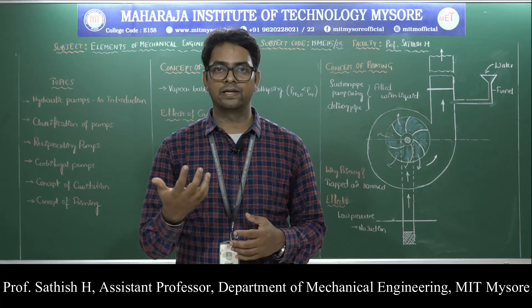One of the effects of cavitation is that it will damage the metallic surfaces. As I said, the impeller or the housing's inside surfaces can be damaged. So in order to avoid that, you should coat these inside metallic surfaces with the help of these metals: aluminum, bronze or stainless steel coatings. Even if the bubbles burst, the coating will prevent the components from damage. So those are some of the precautionary measures you can take in the case of cavitation.